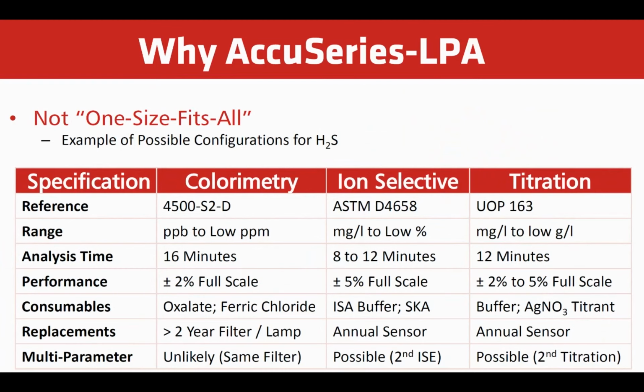Here's just some example configurations for different H2S samples that would measure hydrogen sulfide. So we offer colorimetric for this. We also offer ion selective or titration, and we would use this depending on, obviously, range. It's the most important, but also what kind of interferences would be present. So there is some ions that could be present that would interfere with our ion selective measurement. So at that point, we could either, depending on range, choose to do this with colorimetric or titration.